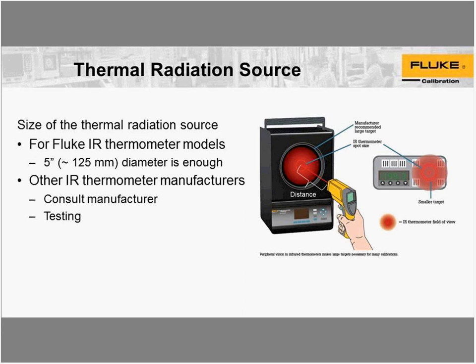For other IR thermometer manufacturers it gets a little bit tougher. You can consult the manufacturer or whoever's name is on the side of the IR thermometer, but likely a lot of these instruments come from OEMs — manufactured by somebody else and labeled with the company's name. So the manufacturer either may not tell you, but more likely they just don't know. The other way you can determine how much space you need for calibration is by doing testing.